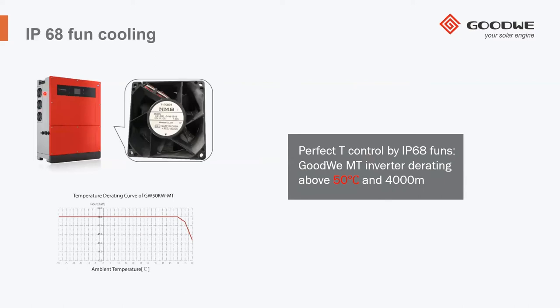Another important feature is the fact, as you can see here, that we have three fans for cooling the system. And the degree of protection of these three fans is IP68, which means an extremely high degree of protection. And the goodness of the electric and thermal project behind our inverter is so good that we can say that we don't have any derating of our inverters up to 50 degrees. And this is extremely important, especially when you consider installation in very hot conditions like you can have on the Greek market. And this capability is due to the very good cooling performance, which is given by the presence of these three fans here.